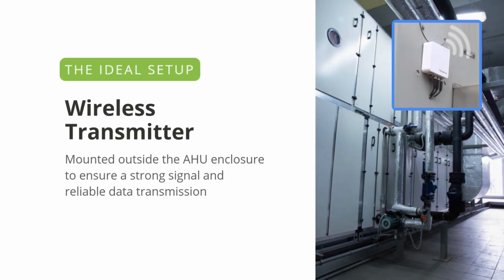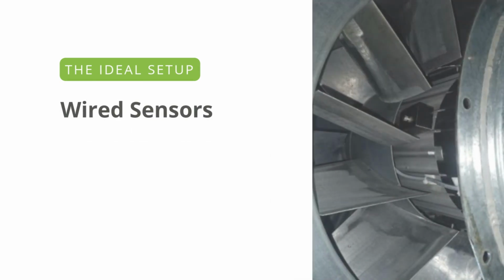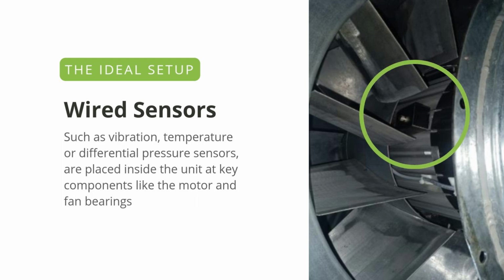So what does an effective AHU monitoring system look like? The most practical and scalable approach uses a combination of wired sensors and wireless transmitters. A wireless transmitter is mounted outside the AHU enclosure to ensure a strong signal and reliable data transmission. Inside the unit, wired industrial sensors such as vibration, temperature, or differential pressure sensors are placed at key components like the motor and fan bearings.